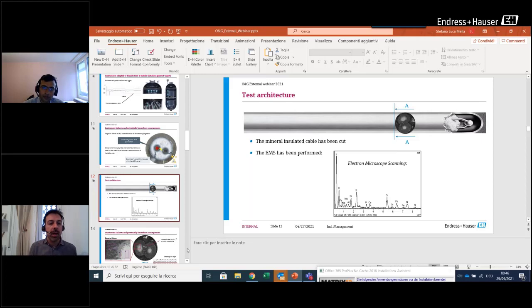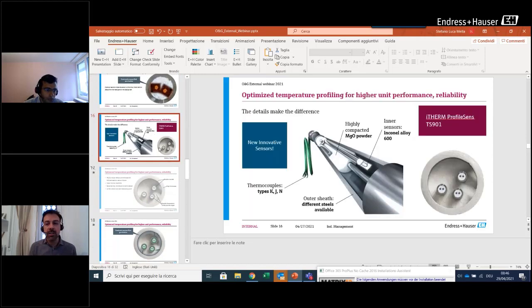With the new ProfileSens technology, we can even do sharper curves because here the limit is 4 times the outer diameter. Why so? Because the inner sensors are very thin and small. Inside we have a powder, and outside just an outer sheath, so when we bend it we're sure nothing inside the probe gets affected. It's an amazing design.